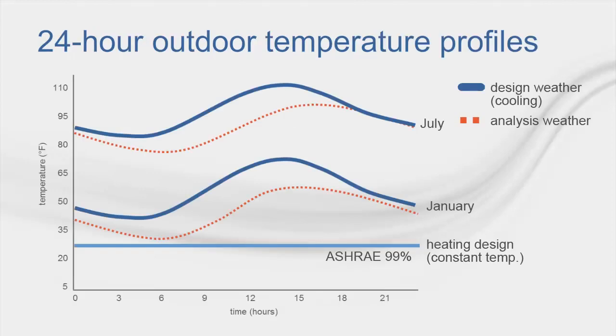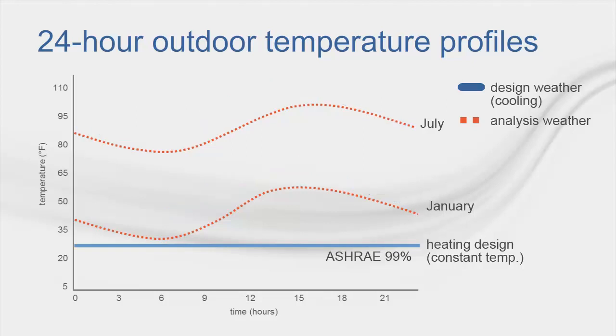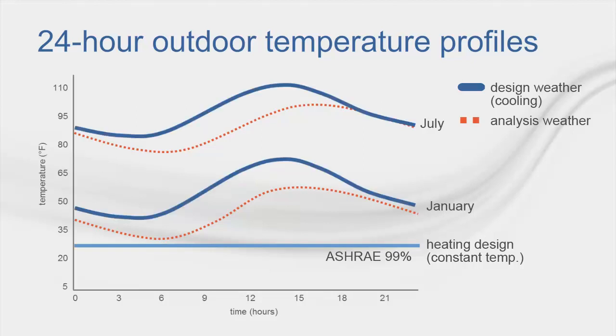There are two major and separate calculation sequences performed by TRACE 700, design and system simulation. The design calculation will determine the equipment demand values using design weather with peak loads. And the system calculation will determine hourly consumption values with hourly loads using analysis weather.